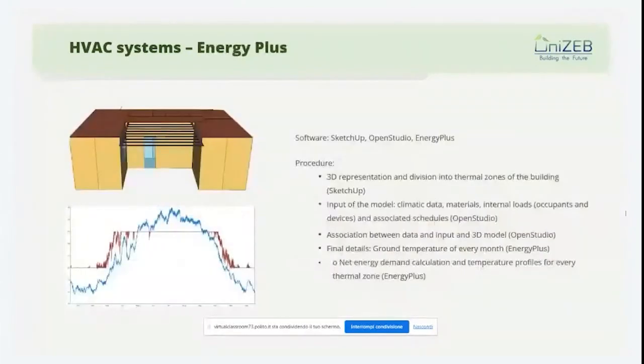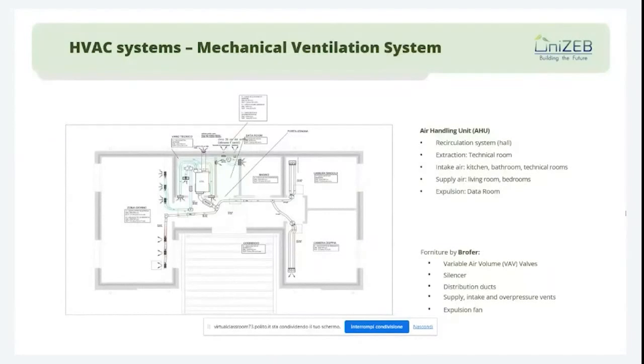Going back, we have some variable air volume solutions, valves, provided by Brofer, a company also working with us. This system is very useful because it allows us to provide air from the mechanical ventilation system according to the real necessity of each room. So we don't have a constant airflow, but can vary it according to the requests of the room or the user.